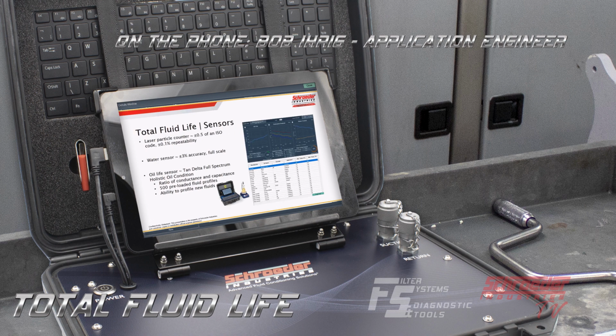I want to mention up front that even though it's called tan delta, that does not have anything to do with the total acid number. What it actually does is it takes the ratio of conductivity and capacitance of the fluid you're processing and relates that to a new fluid profile or new fluid condition, obviously relating to the conductivity and capacitance, or that ratio, of that new condition.